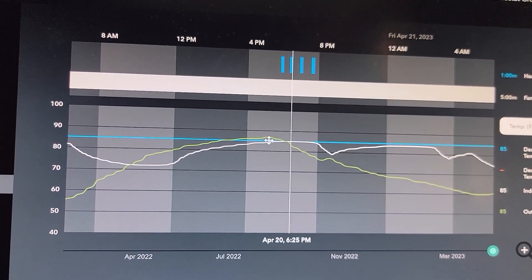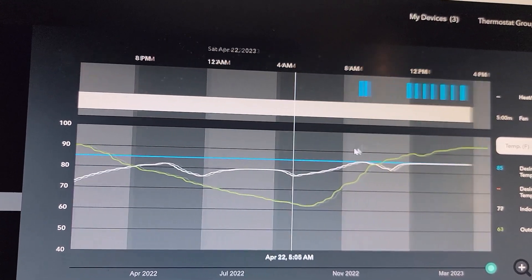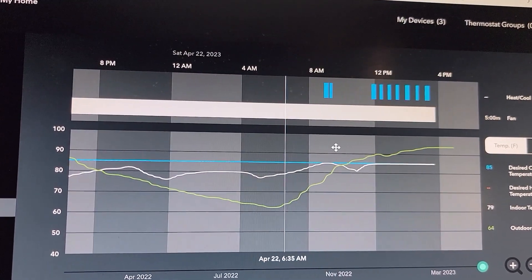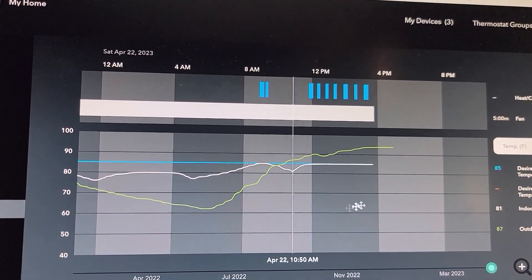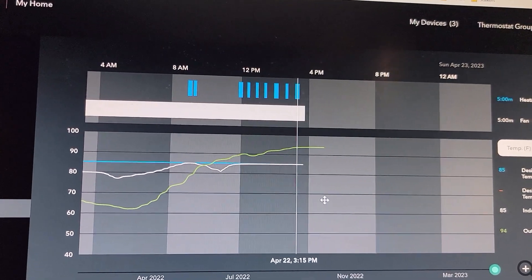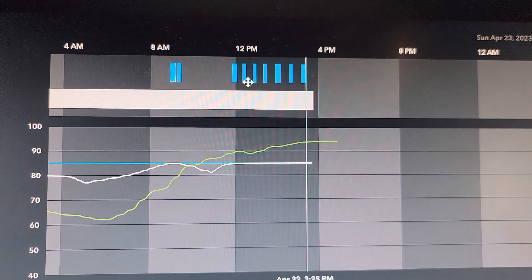You can see these lines where the water heater is not running but the space temp gets above the set point of 85 and it pulses — runs the compressor every now and then. Most of the time I haven't been using the room and it doesn't really need to turn on via the thermostat to cool the room, except when it gets a little warmer. The morning shower recovery was today, and this afternoon it's been running normal cycles. It's about 94 degrees outside right now, and as the outside temperature has warmed up and the inverter is running in there, it's just been cycling the compressor.